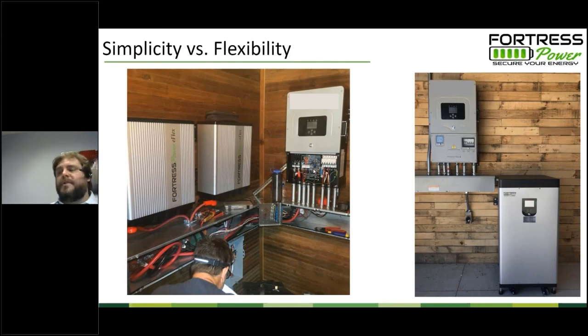It's 18 kilowatt hours instead of 5 kilowatt hours. They're all machine welded inside that battery. Fewer connections, fewer parts, more capacity, results in a lower cost per kilowatt hour compared to the eFlex. And in fact, the eVolt, being 18.5 kilowatt hours, is designed to skip all the combining. You can just take an eVolt and land it directly onto an 8 kilowatt battery inverter, and the money that you would normally be spending on combining material goes straight into the battery. So you're getting more bang for your buck with the eVolt.